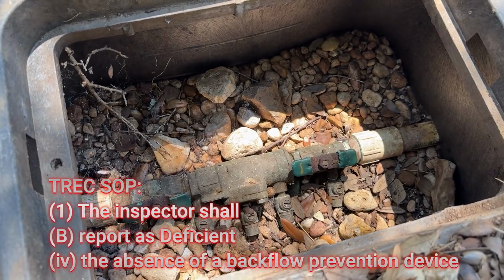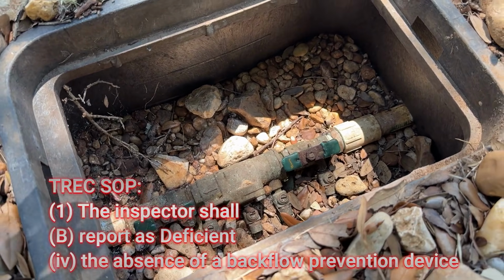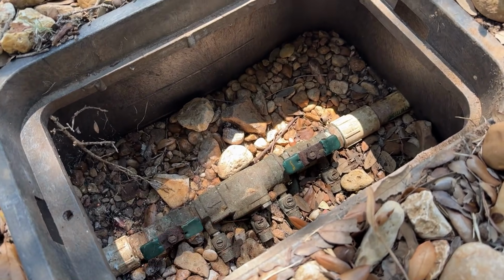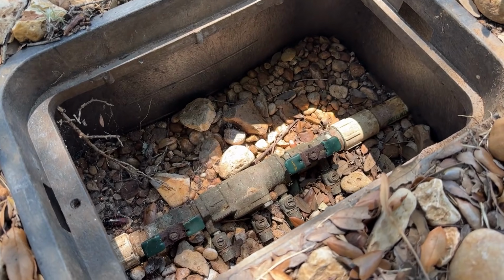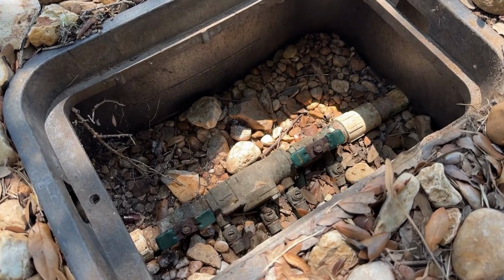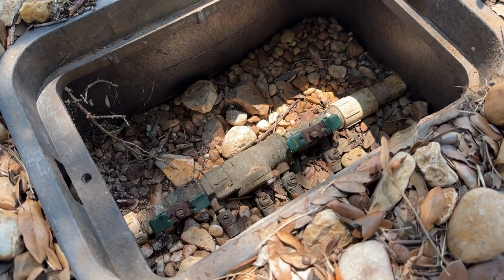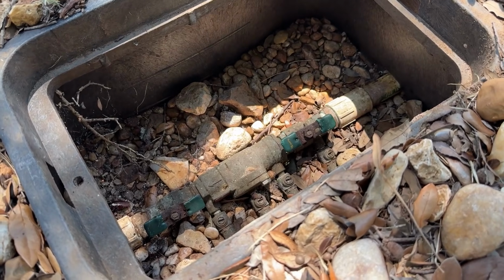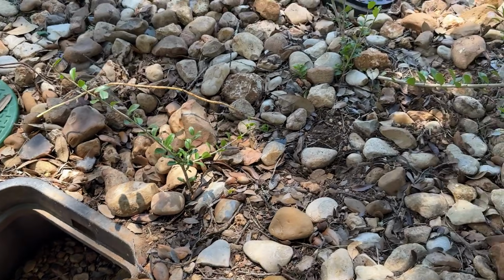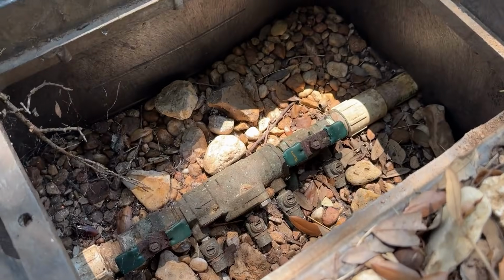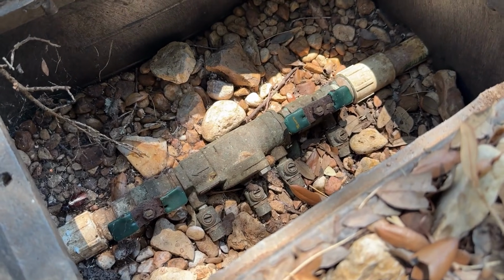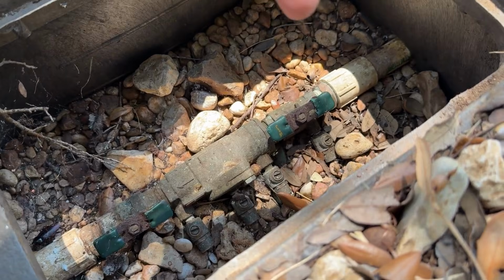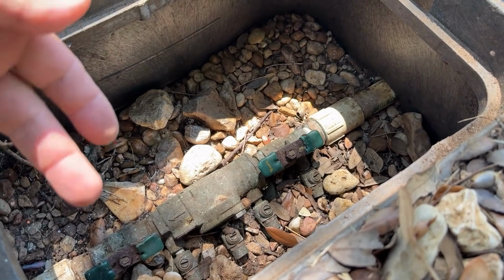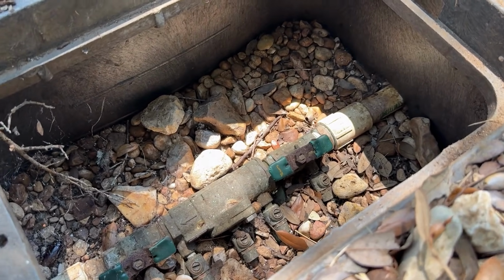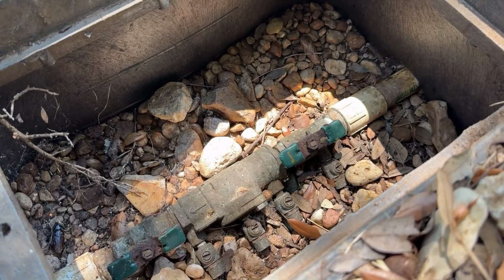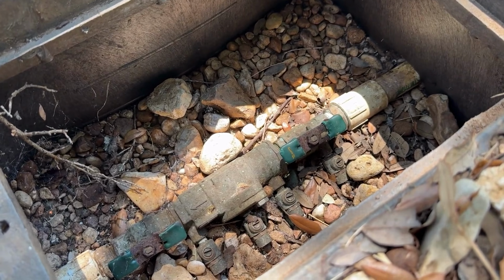It may look familiar, but that is basically one of the primary required devices as part of the sprinkler irrigation system inspection. This is essentially our safety device that prevents us from having a potential cross-contamination of water between contaminated water and our city supply water coming into the house. Now, the way these devices work is their internal components allow water to pass through in one direction only, but does not let the water go back in the reverse direction, whether that be due to a sudden pressure drop in the water line or for whatever reason that may be.